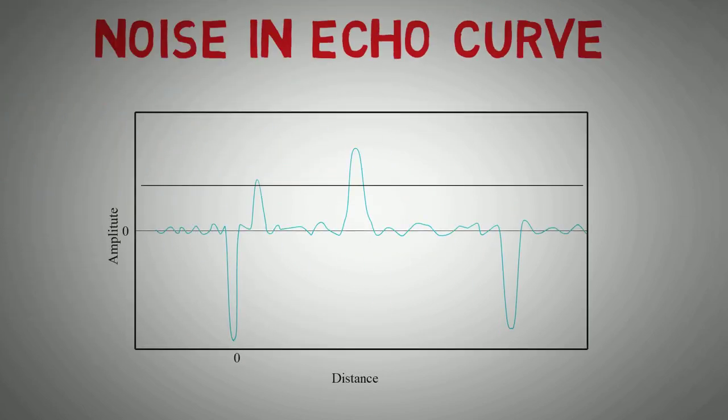Noise can sometimes cause false level indications by the transmitter. Rough nozzle edges can cause unwanted reflections. Here in this example we see a positive indication near the beginning of the probe caused by the vessel nozzle that is being read as a false level.